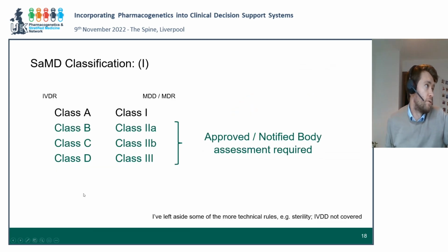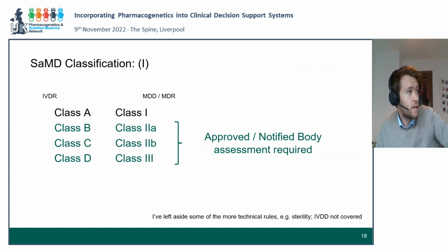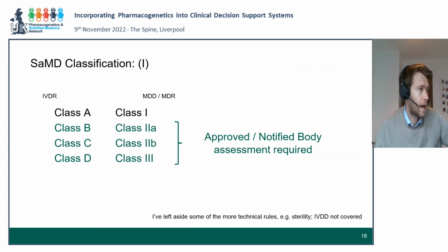So software classification under the IVDR, under the current directives and also the EU MDR: if you're class 1, that means you're self-assured. You do not have to go through a conformity assessment body, the CAB system. If you're 2A and above, then you must go through that system. In the IVDR, if you're class A, and as long as that's a non-sterile device, for example, then you do not have to go through that system. You can be self-assured, but if you're class B, C, or D, then you have to go through that system. That can add extra time and expense, but that is how the system currently works.